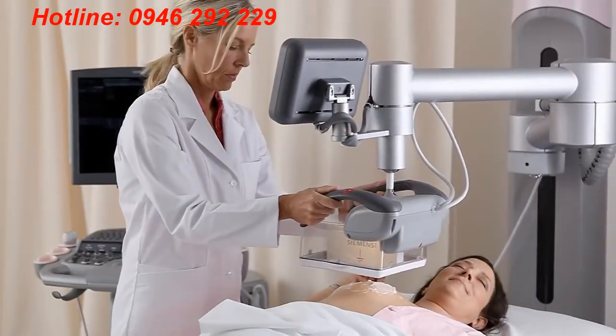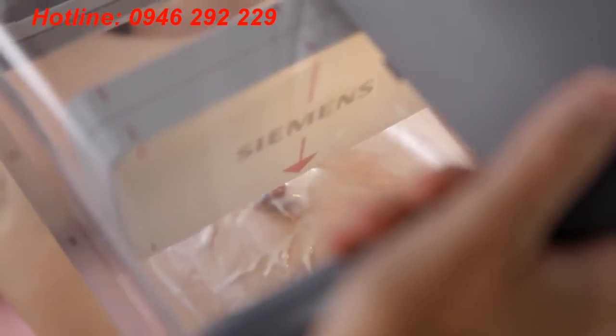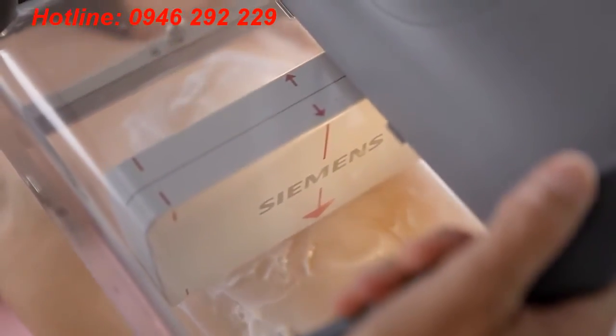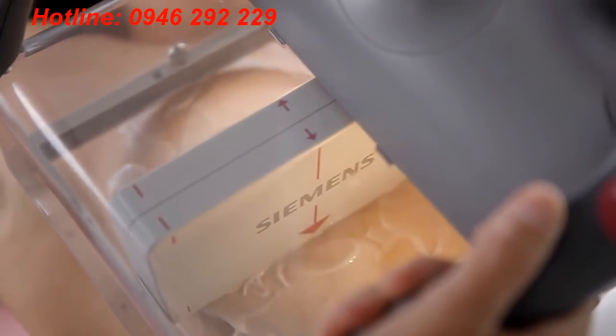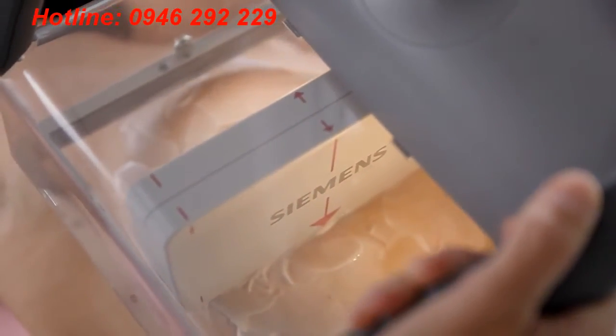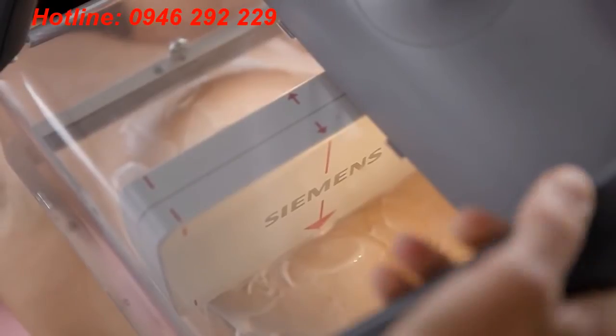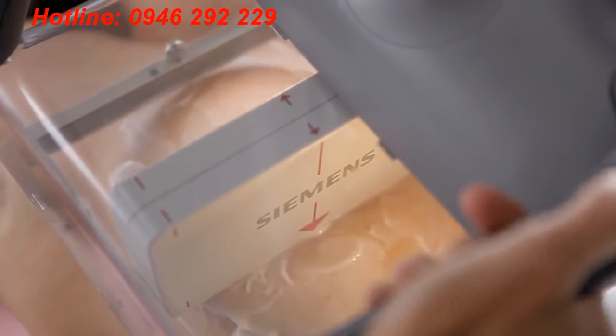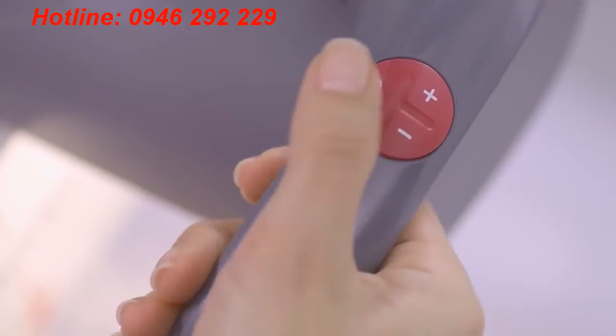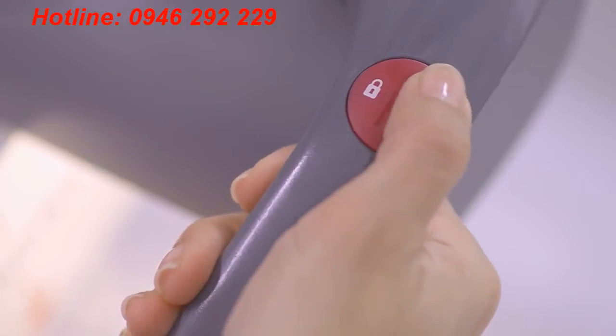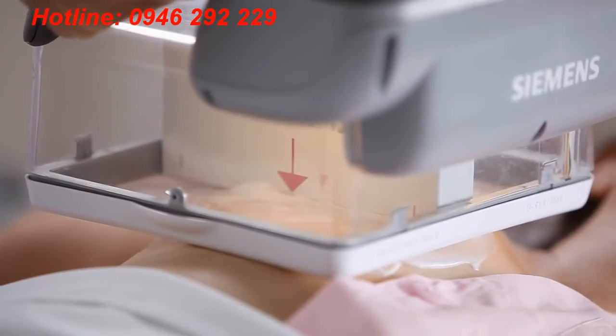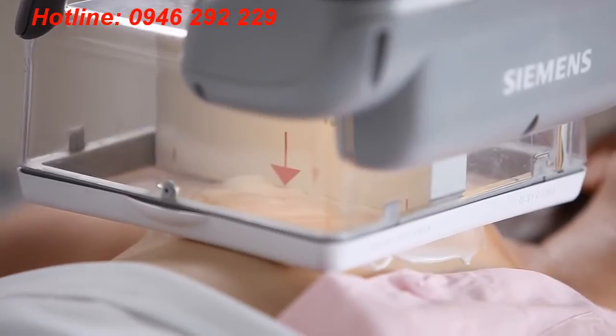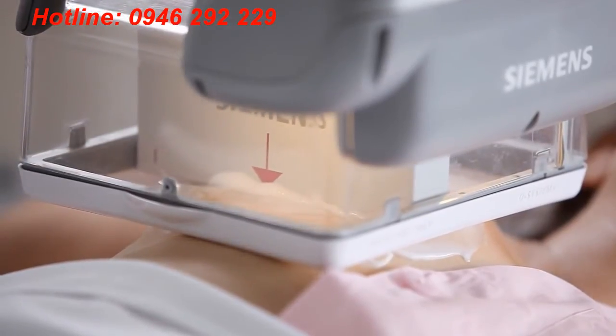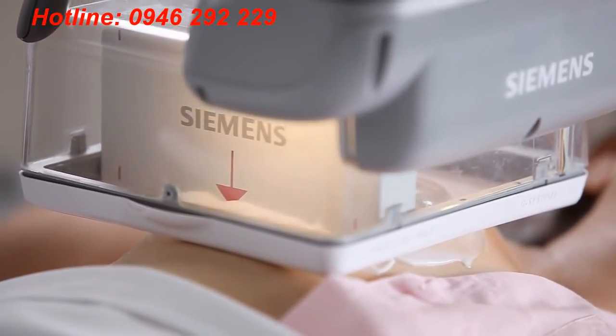For the first AP view, I'm going to bring the transducer pod across her body and center it over the breast. Using the pink arrow in the middle of the transducer as a guide, I center over the breast, but not necessarily the nipple, and sometimes the nipple is not the center of the breast. I lock the transducer pod in place and apply a small amount of compression, and that's usually no more than 1 to 2 steps. And I do this using the automatic compression button.